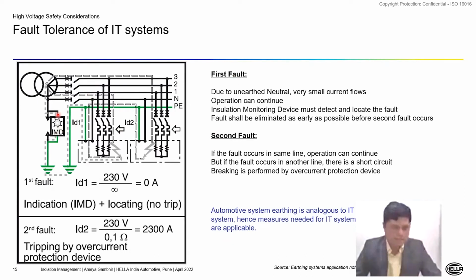Okay, but it is expected that this IMD, which is sitting here between neutral and earth, should detect this and should also locate the fault. If we are able to eliminate the fault as early as possible, then there is no chance of creating a second fault. Now, in an IT system, let's consider that the second fault occurs. So the first fault has already occurred, but probably it got undetected and there was no harm. But now in the second fault, there is a very high danger of short circuit as well as harm. You can see the currents in the second fault, because now the second fault is directly creating a short circuit. The currents could be as high as 2300 amperes. And basically, if the fault occurs in another line, then there is a short circuit hazard. Automotive systems are derived from IT systems, and that's why whatever measures are followed in the industrial domain for IT systems are applicable in our domain, the automotive domain.